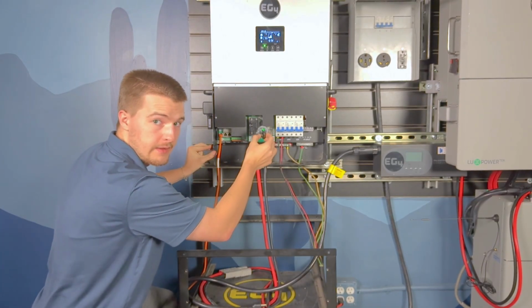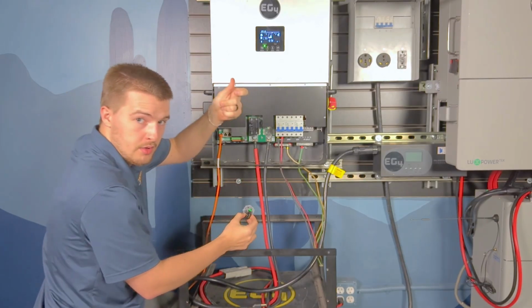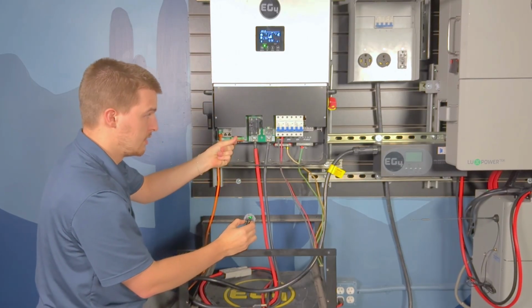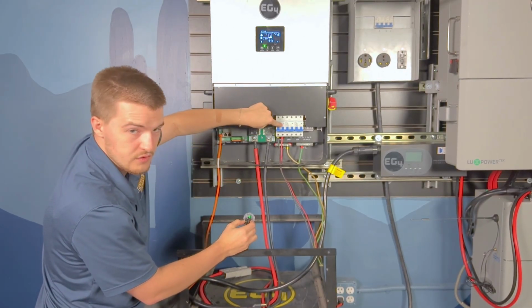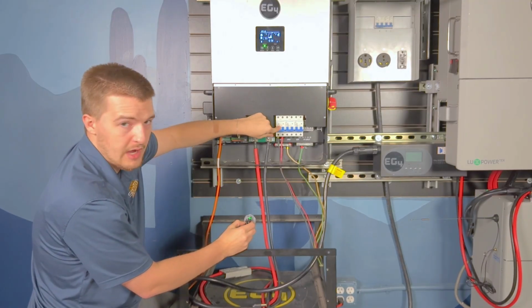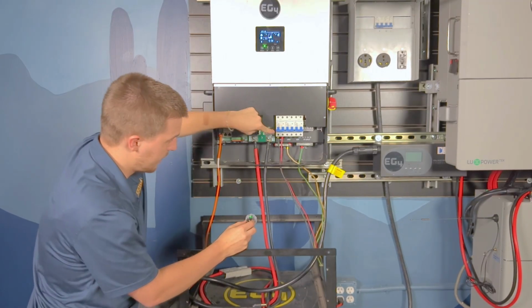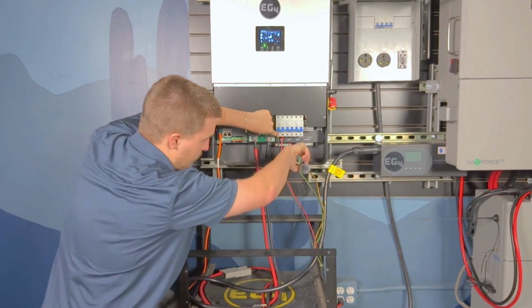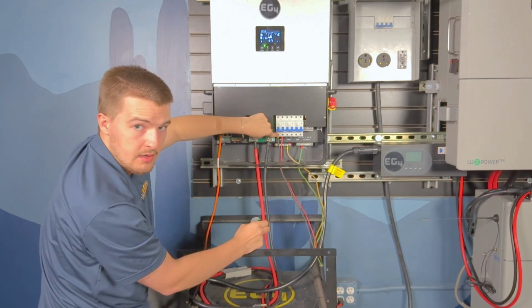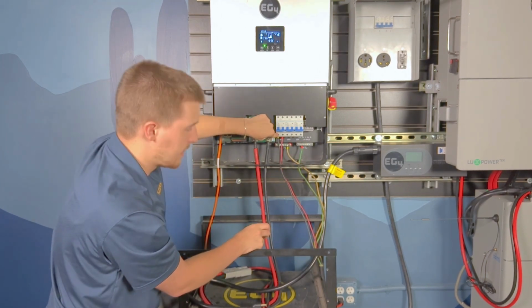I really hope you heard that click, because you hear the beep and you hear the click. The click is what turns this on. If I test it for voltage right now, it will give me 240 volts. And if I test one leg here and one leg on a neutral, it'll give me, you guessed it, 120.